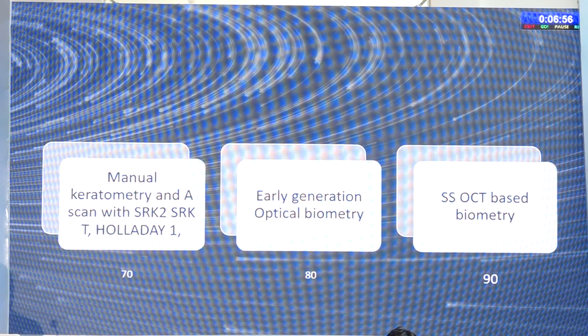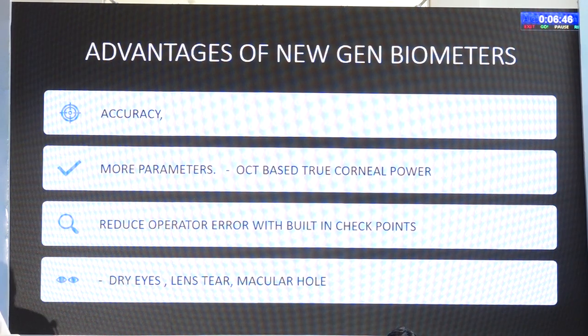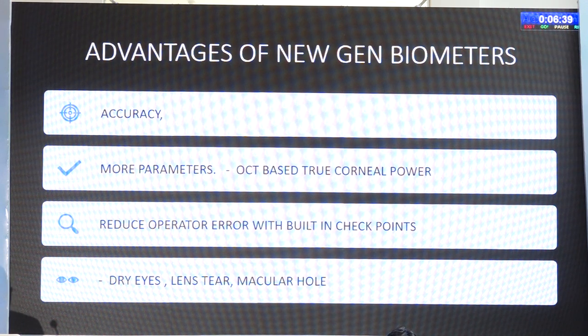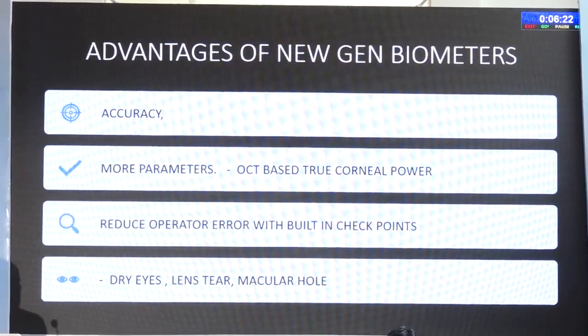Axial length is no longer the issue, but the cornea is the issue and this has been extensively covered in the last few years. We have to optimize the cornea before taking measurements. The advantage of newer generation biometers is that they are more accurate for the cornea, we get a whole set of new parameters, and we can get a true corneal power by OCT-based machines which measure the front and back of the cornea. Mistakes the operator makes are reduced because machines have checkpoints.